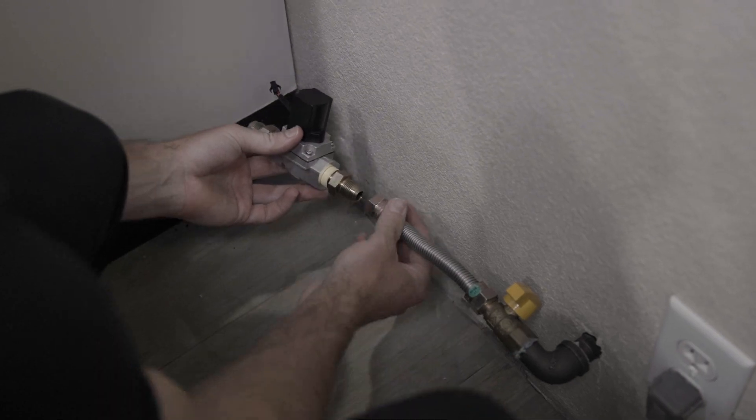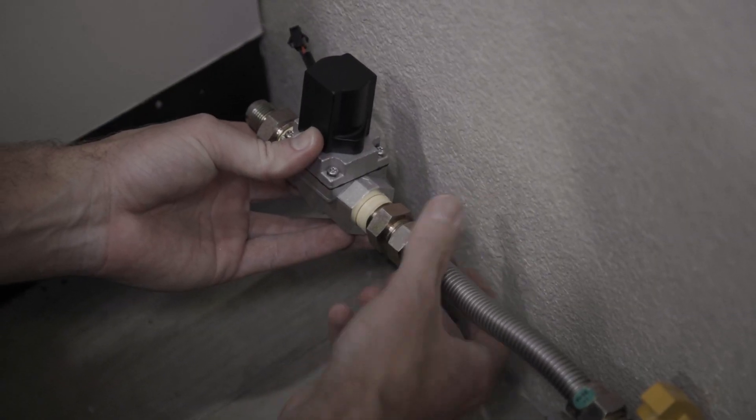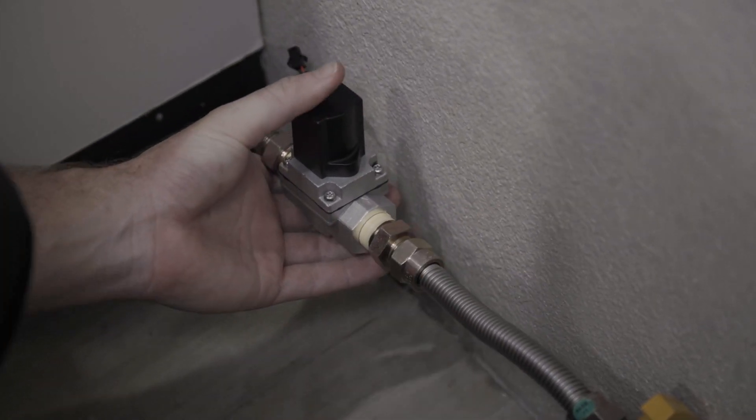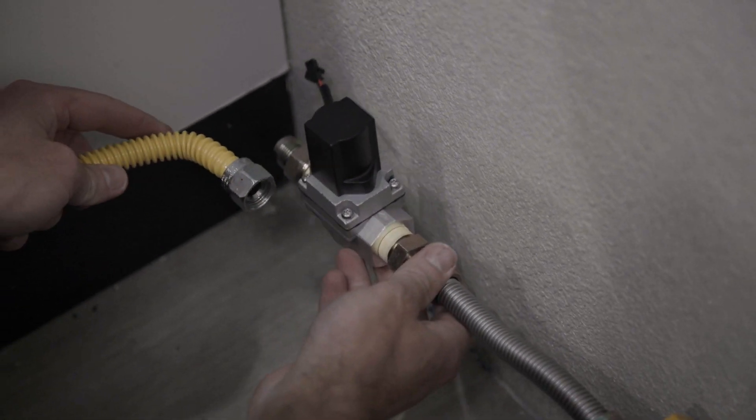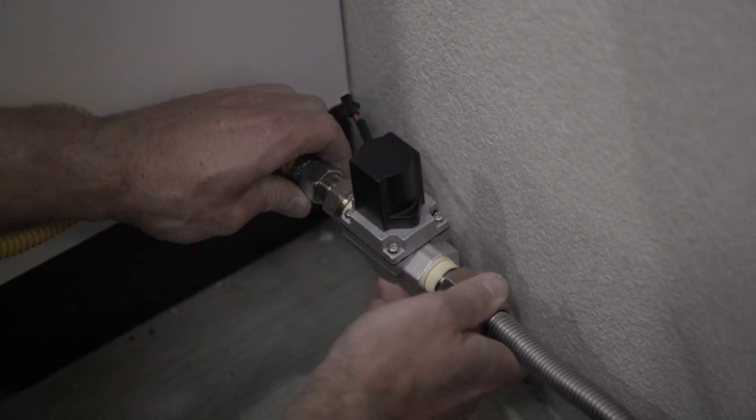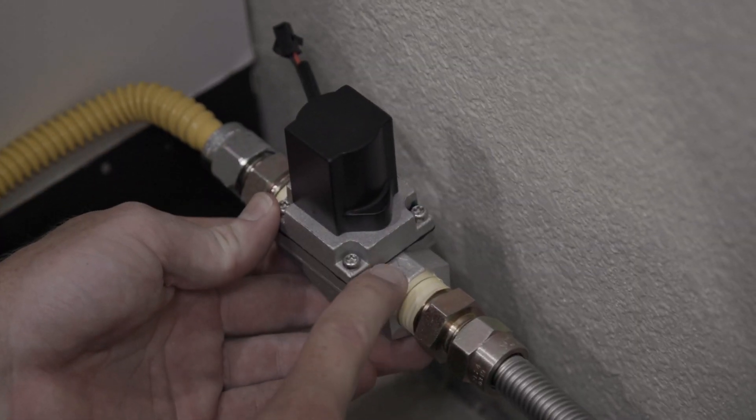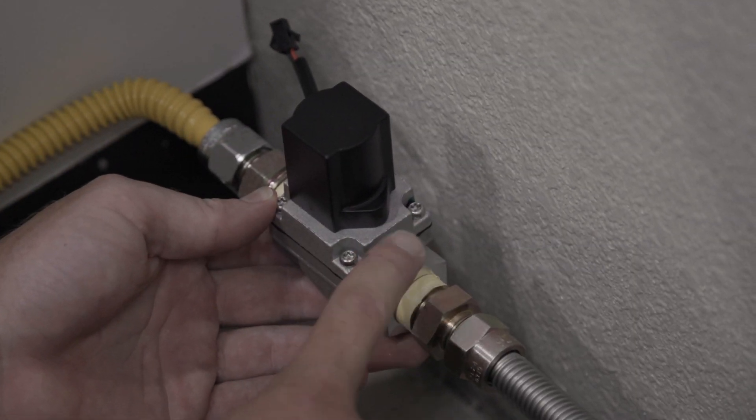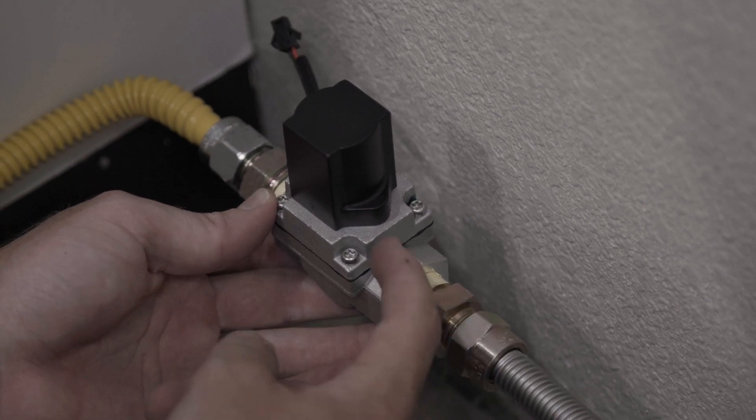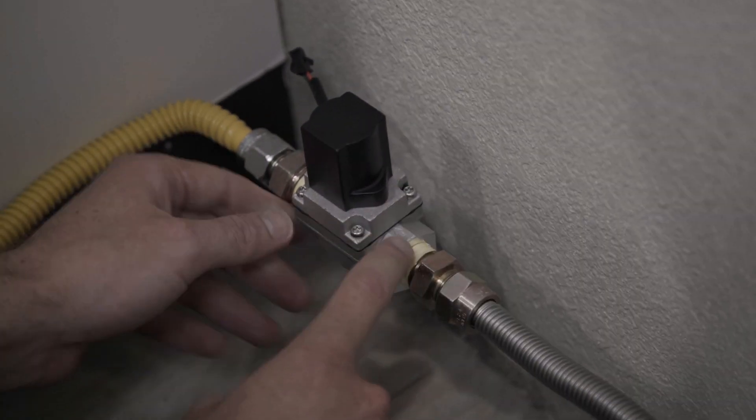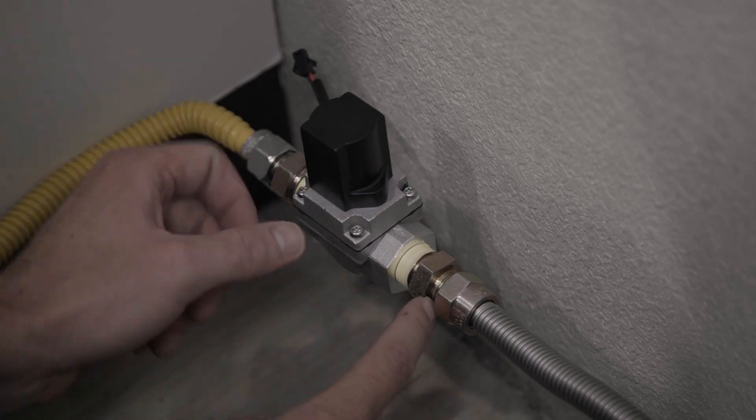Now you're going to take the solenoid and connect it to the flexible line that you installed. Next, connect the oven hose line to the other end of the solenoid. It's important to check on the solenoid. The arrow is in the direction of the flow towards the oven. If it's installed backwards, the device will not work.